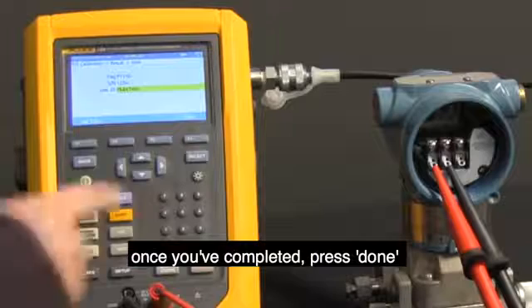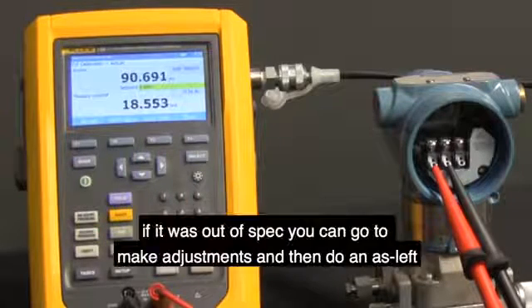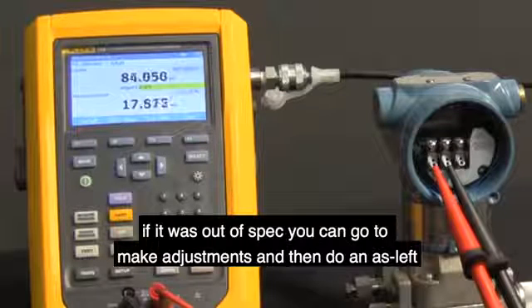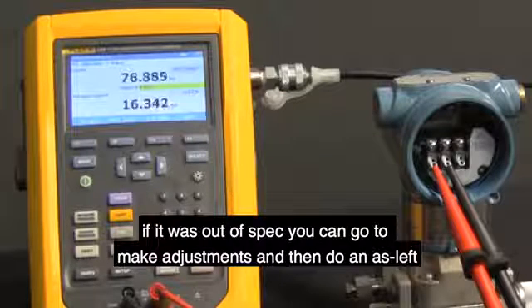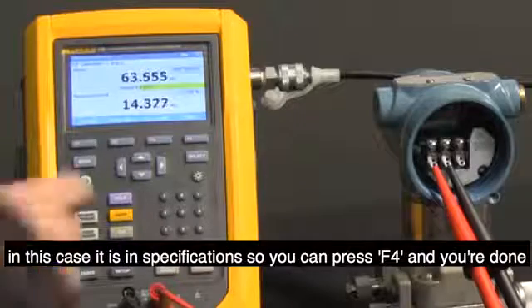Once you've completed, press done, and now the calibration has been documented. If it was out of spec, you could go to make adjustments and then do an as left. In this case, it is in specification, so you can press F4 and you're done.